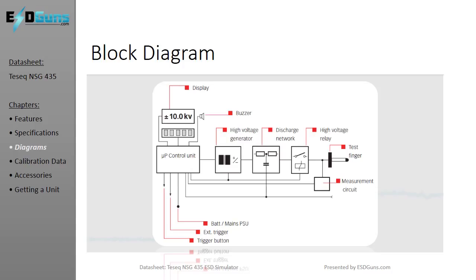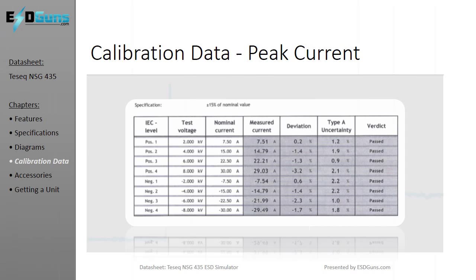Acoustic signals will occur to confirm parameter inputs, termination of test sequences, and warnings. A measurement facility at the pulse output measures the actual air voltage reached during an air discharge, and it will show on the display. Pulse triggering is also monitored. Once an arc has occurred, the network is discharged internally so that no further arcing is possible. The following 4 charts contain sampled calibration data including peak current, rise time, DC voltage for air discharge, and the output curve. For in-depth analysis, you will want to pause this video.